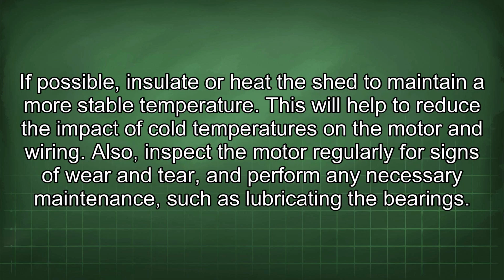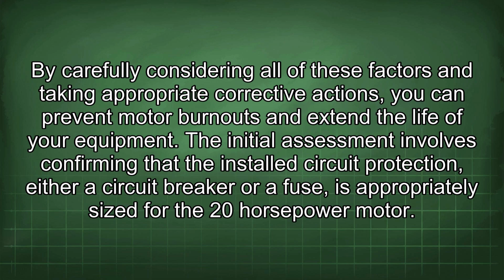If possible, insulate or heat the shed to maintain a more stable temperature. This will help to reduce the impact of cold temperatures on the motor and wiring. Also, inspect the motor regularly for signs of wear and tear, and perform any necessary maintenance, such as lubricating the bearings. By carefully considering all of these factors and taking appropriate corrective actions, you can prevent motor burnouts and extend the life of your equipment.